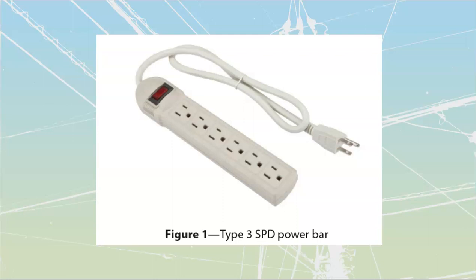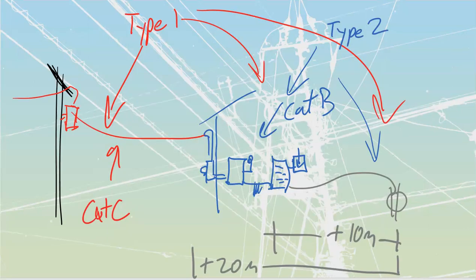Cascade surge protection is where, as I work throughout my installation, I'm going to have multiple surge devices. I can have a surge device somewhere out here that's going to be Cat C type 1. I can have another surge device hanging in the middle of the line. Why don't I place it by something here? We'll put that right up there. I could have a Cat B somewhere over here. We'll make it Cat B. And I could have another type C, a plug-in type, all the way over here inside of my category A.